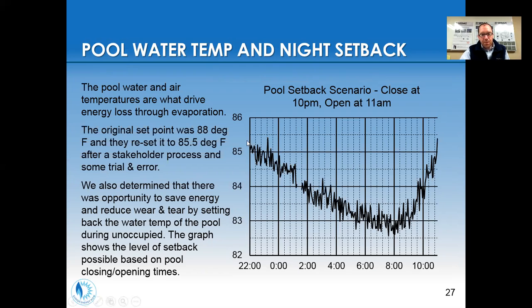Also in this graph, we were able to do some tests where we were setting the pool back. They were closing at 10 and then opening at 11. And on the days that was applicable, they were able to set up a schedule where their boiler changes the water temperature overnight, and it sets it back. By just coasting, it lost about 2 degrees, and then it was able to make that up within 2 hours in the morning.